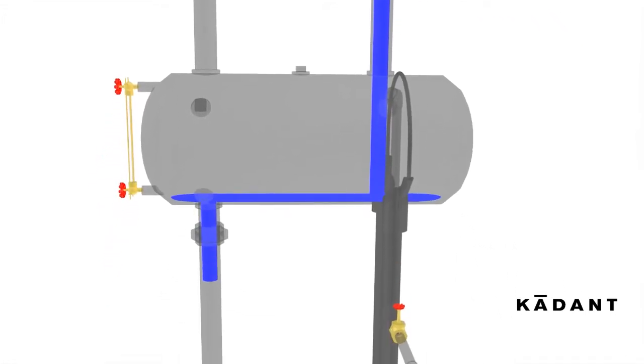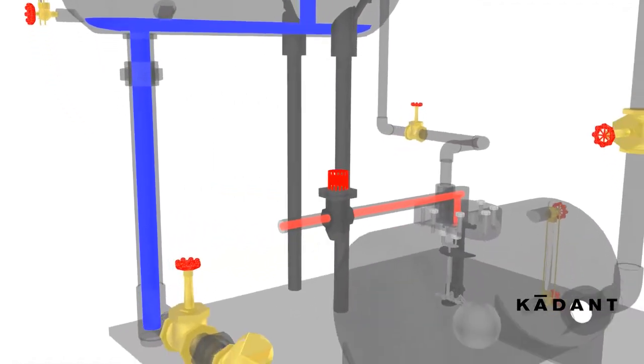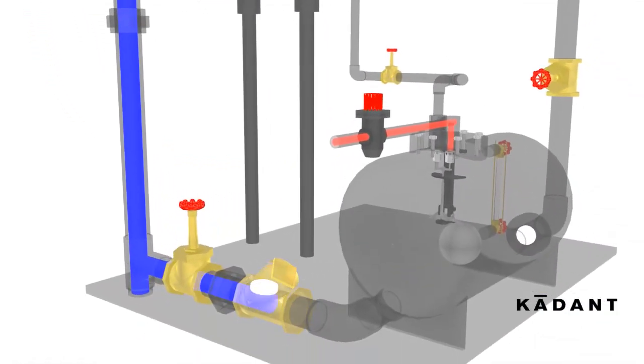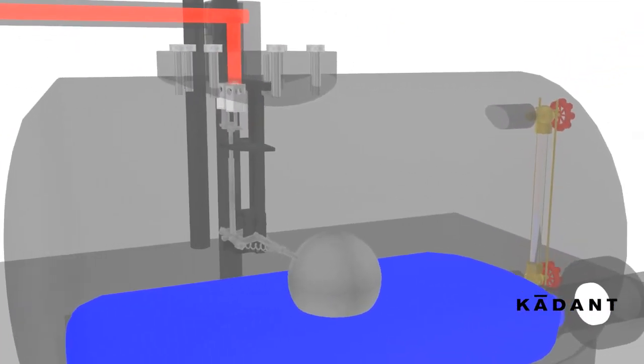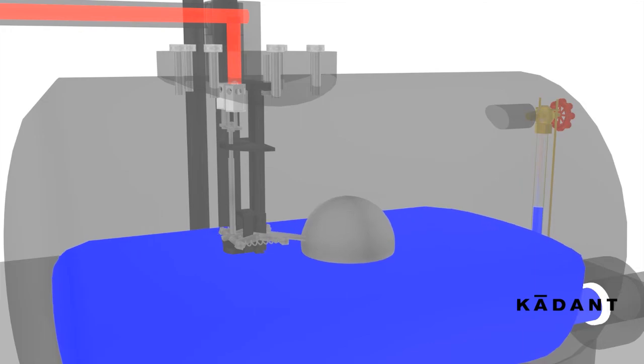Condensate flows down the fill line, through the inlet check valve, and into the liquid mover pump tank. The outlet check valve is closed due to back pressure, allowing the condensate to fill the pump tank.